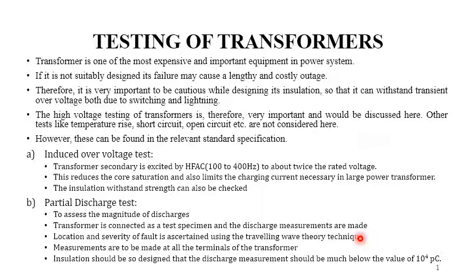There is an incident wave which goes and comes back. So two different waves reach the measuring devices, and there is a time lapse between them. Based on that, we identify the location of the fault, and the waveform, that is, the shape of the waveform. Based on that, we can understand the severity of the fault or the nature of the void.